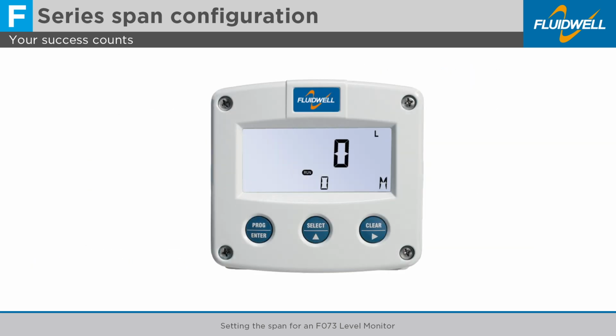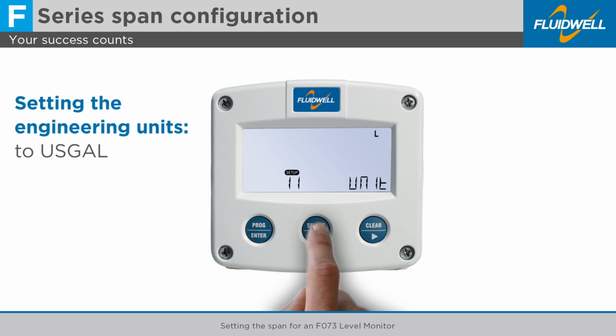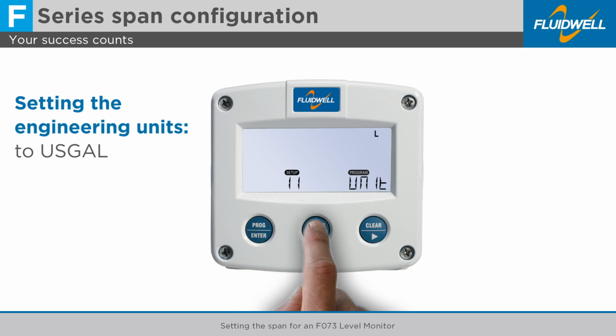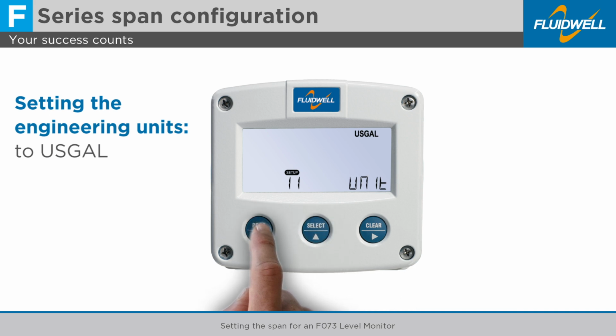Hold the Program button for 7 seconds. Menu 1 Level appears. You can use the Clear and Select buttons to navigate through the menu. Use Select to go to Menu 11 Unit. Select the engineering unit for level. Press Prog to change this setting. Select USGAL for US gallons. Press Prog to store this setting.